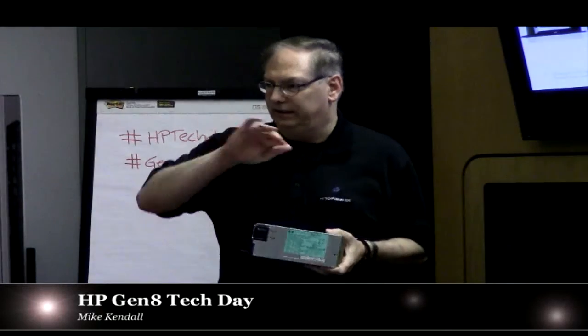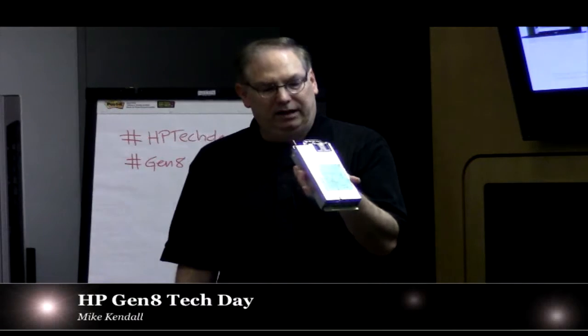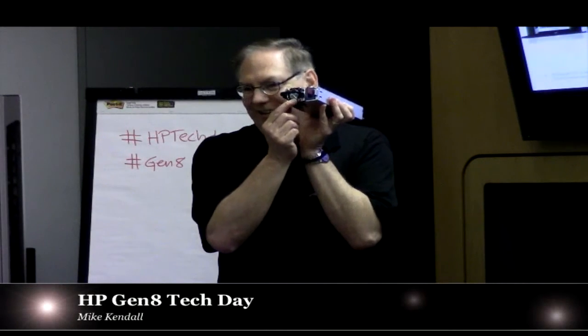What that means is at 50% load, if you look at an efficiency curve, these are able to convert - you put in 100 watts, you get 94 out the backside that goes actually to the server. Now there's several ways you can identify a 94% power supply from HP: first, it says 94% right there. The second thing is all of our 94% power supplies, called Platinum by 80 Plus, have this blue connector on there - I'll explain more about the significance of the blue connector in a couple minutes, but that's the fastest visual identifier. The other thing too is we have a minus 48 volt version of this.